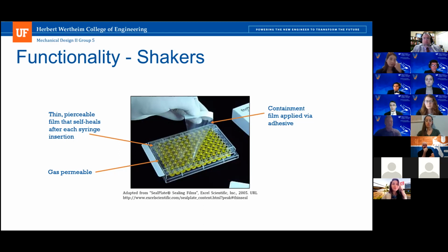Perhaps I can elaborate a little bit there. The customer needs themselves specified that we would have to control the composition of the air, 5 different gases inside the chamber. And this sealing film is a proprietary material. I believe it's called Aero Seal. The data sheet says it's very permeable for general air and carbon dioxide.